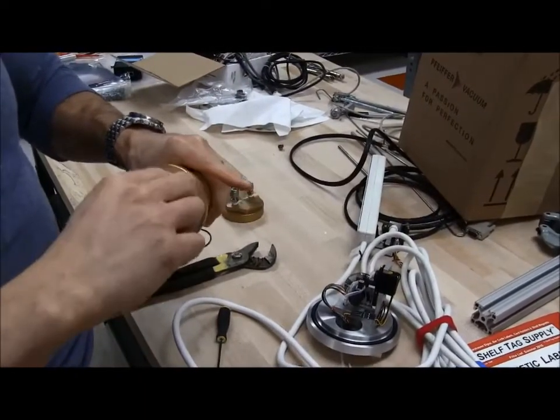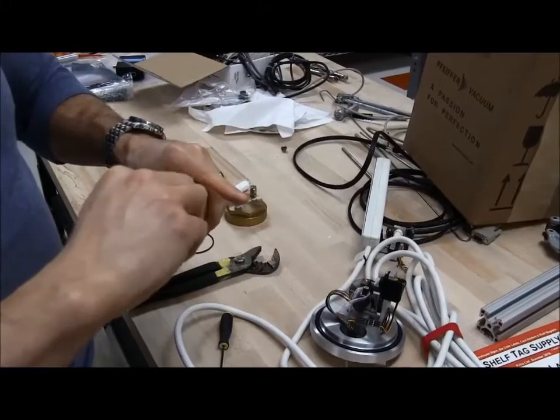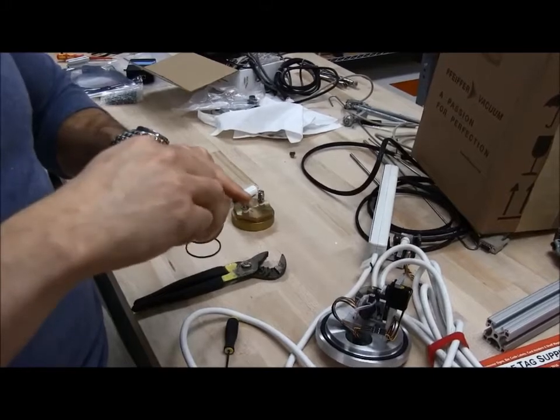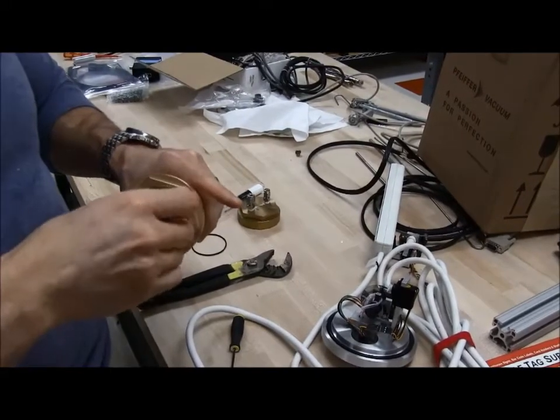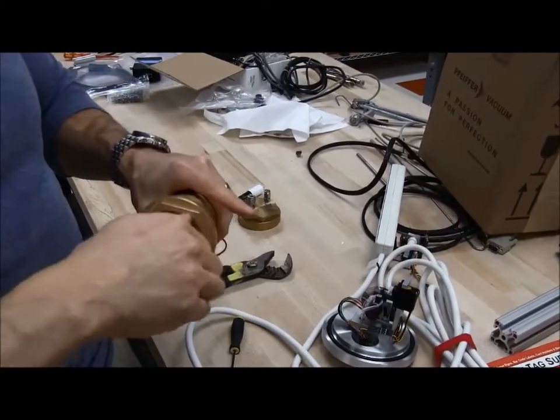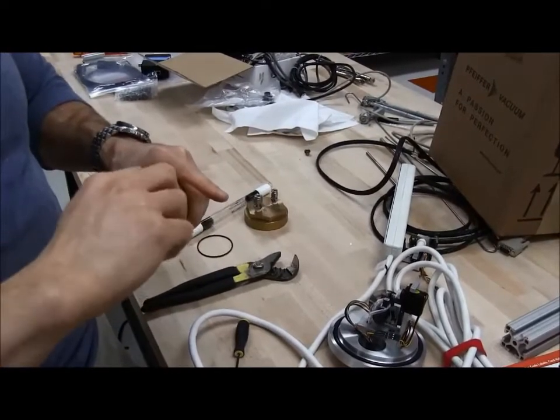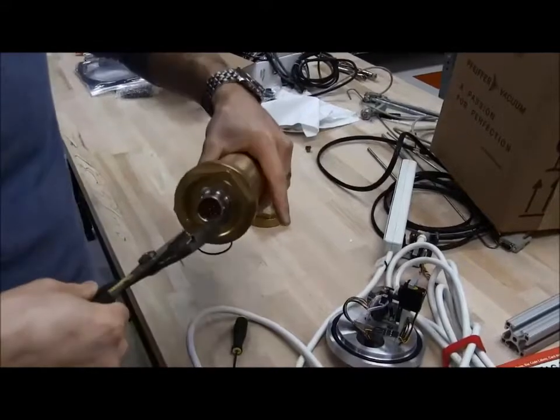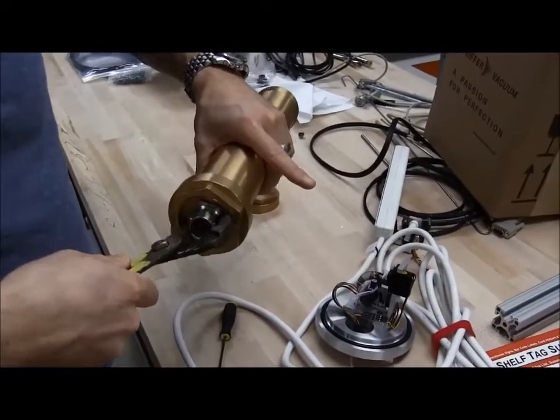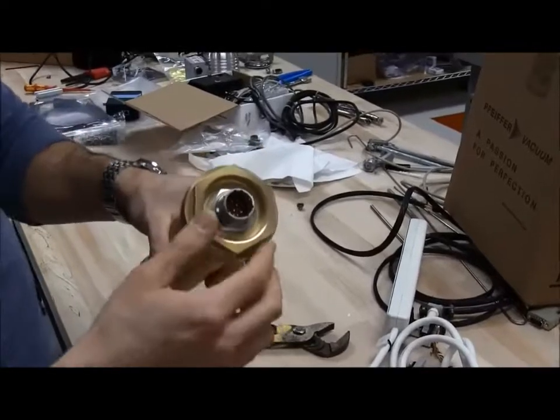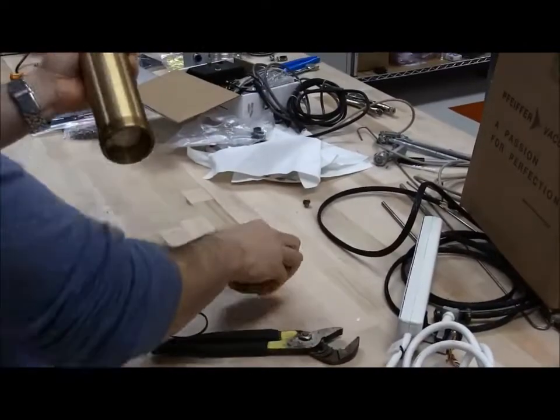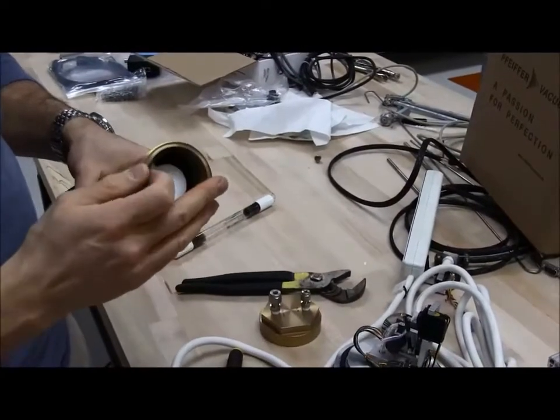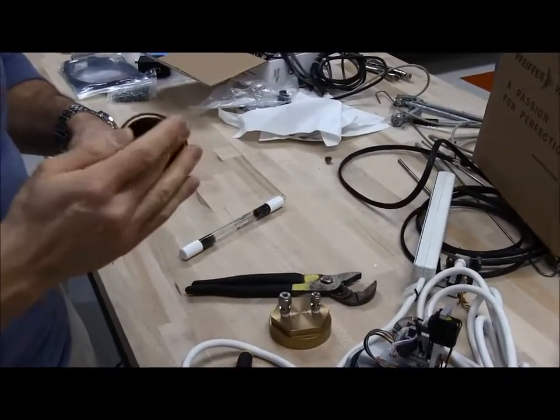And you can just put the nut back on. That blue O-ring has to sit on the groove on the inside so when you're reassembling it try to keep the ozone chamber straight up and down as much as possible so it doesn't slide out. So you can just finger tighten this. Gently tighten it with channel locks over the socket and then the other side if the O-ring fell out just put it back in.